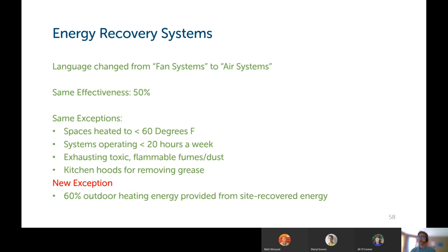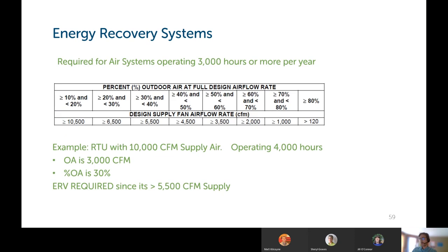There are a lot of the same exceptions, like spaces that are heated to a maximum of 60 degrees do not need energy recovery, systems operating less than 20 hours a week. If you're exhausting toxic or flammable fumes or dust, you do not need it. Kitchen hoods that are removing heavily grease-laden air do not need energy recovery systems. And there's a new exception in here for if 60% of the outdoor heating energy is provided from site-recovered energy, you do not need energy recovery systems. So energy recovery systems are required for air systems operating 3,000 hours or more per year.